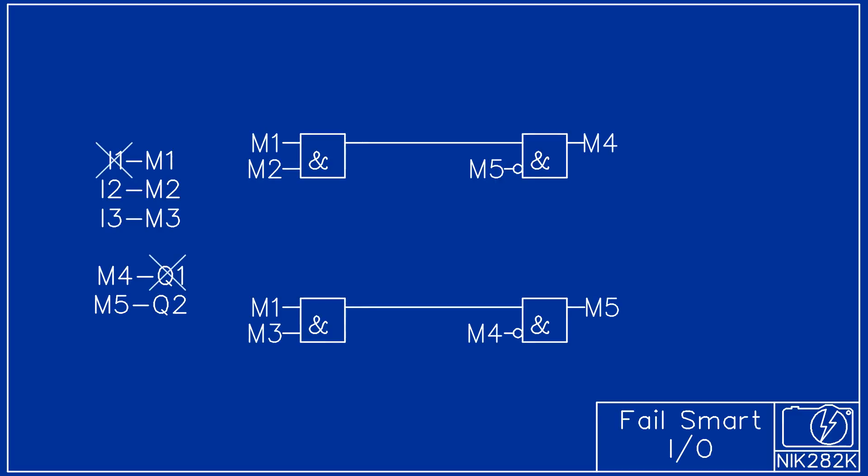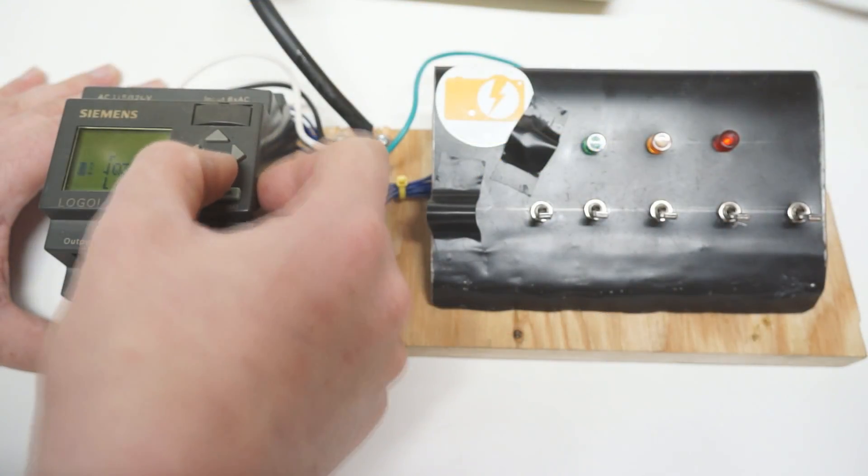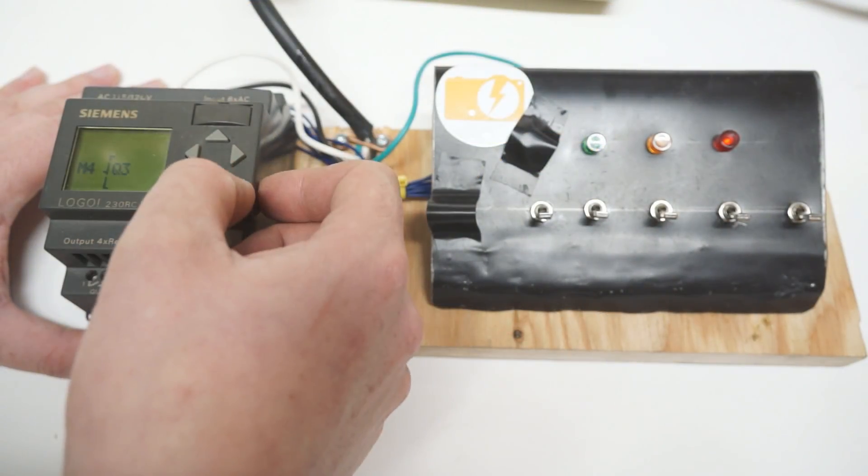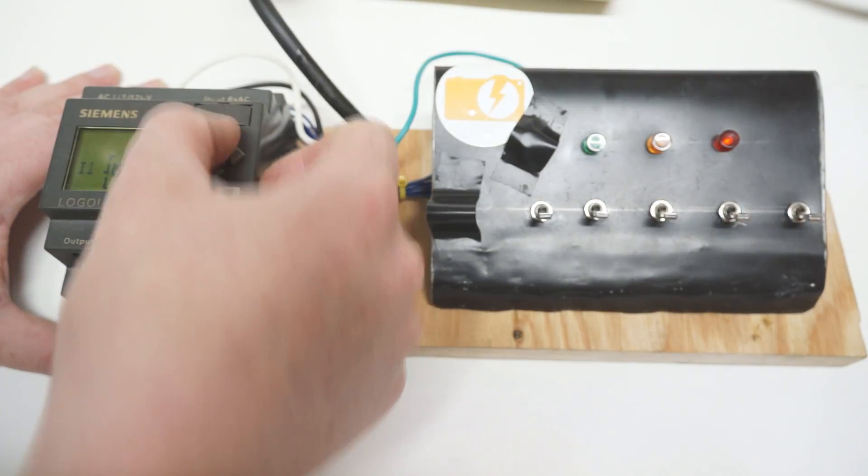If a fault were to occur in I1 and Q1 the recovery process is now very simple. Instead of replacing every reference to I1 and Q1 in the program only the two memory bit assignments need to be changed.